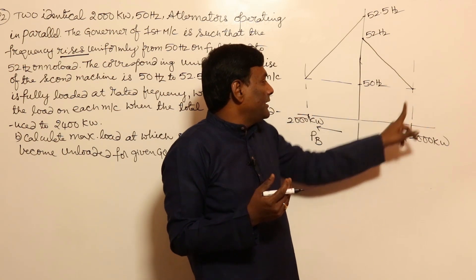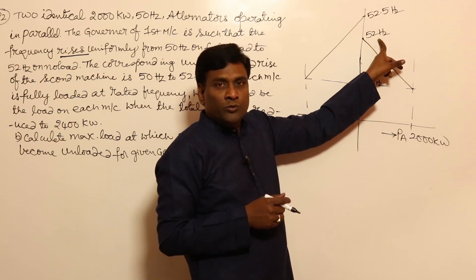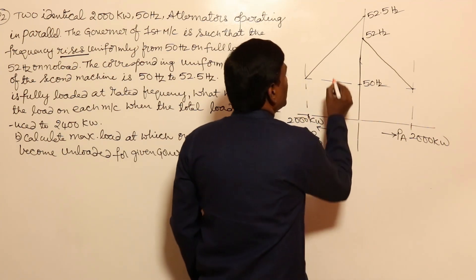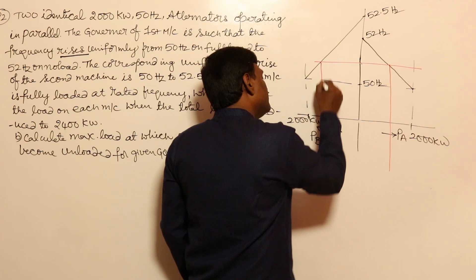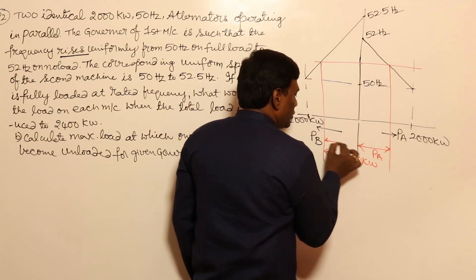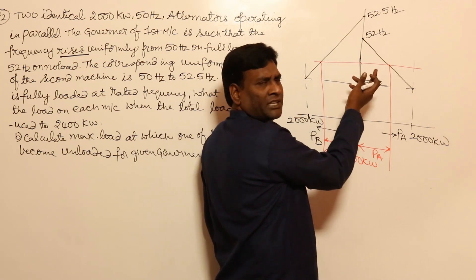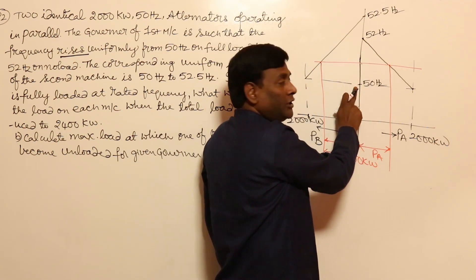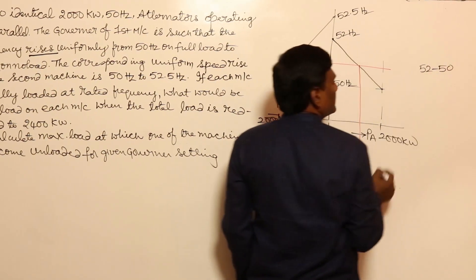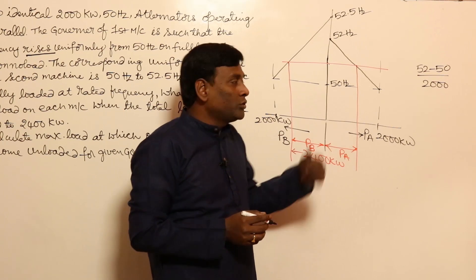Both machines are operating at full load at 50 Hz. If you keep reducing the output power, speed or frequency rises due to speed regulation — frequency rises to 52 in one case and to 52.5 in the other. The total output is now 2400 kilowatt, which equals Pa plus Pb. We need to write two equations to solve this.